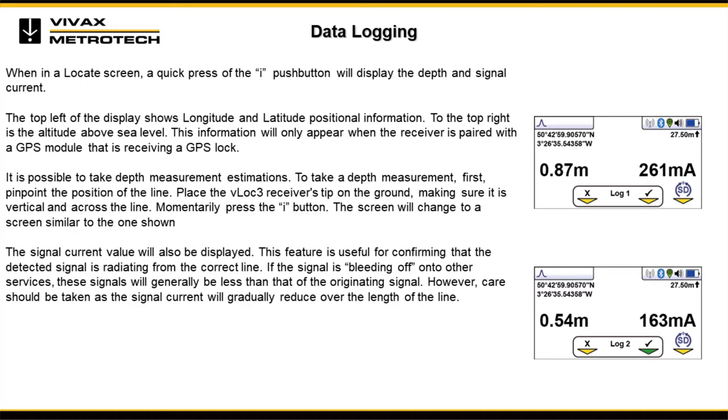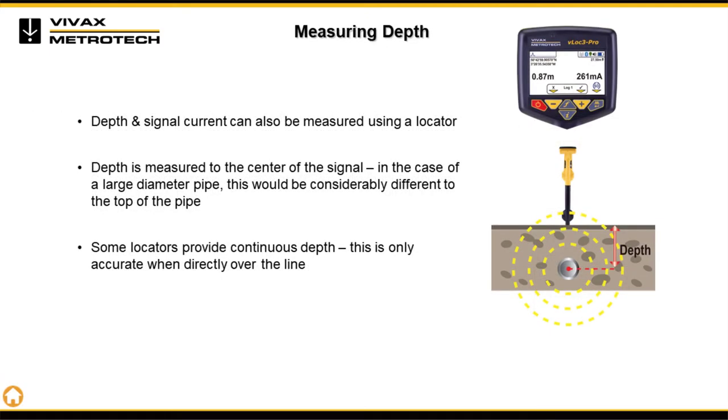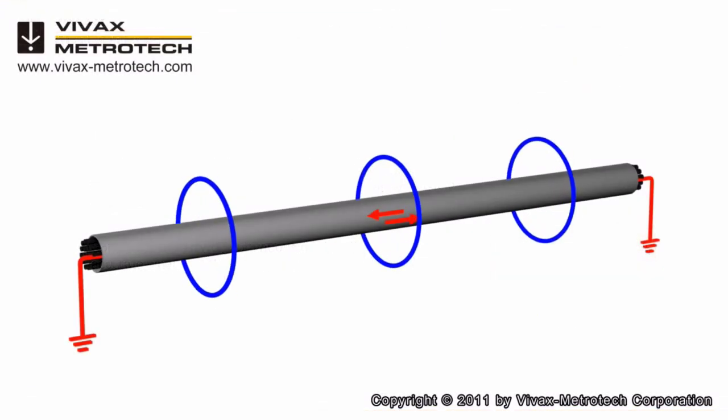It is possible to take depth measurement estimations. To take a depth measurement, first pinpoint the position of the line. Place the vLoc3 receiver's tip on the ground, making sure it is vertical and across the line, then momentarily press the I button. The screen will change to show the depth reading, and the signal current value will also be displayed. This feature is useful for confirming that the detected signal is radiating from the correct line, as signals bleeding onto other surfaces will generally show less current than the originating signal. Note that signal current will gradually reduce over the length of the line.